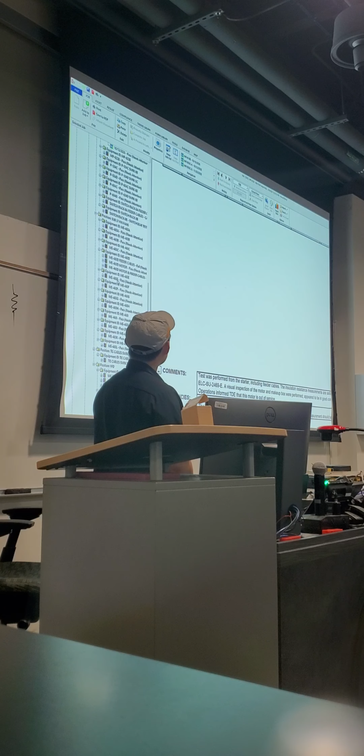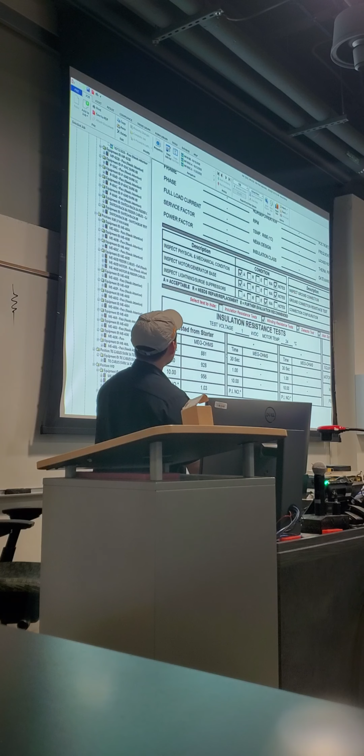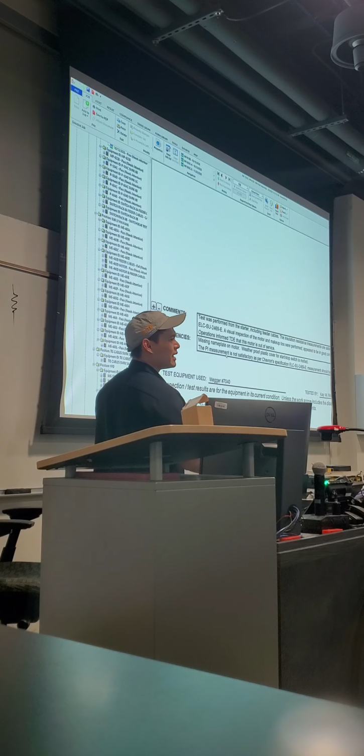I think for extra, you put a missing nameplate on the motor. Yeah, missing nameplate on the motor. And so, in this case, maybe we have historical data or maybe a sister motor and we'll know the system well enough from one line and stuff to be able to say, okay, this is your nominal, so we know to test it at this. But if it burned up in the fire or is illegible, well, standard 20% overage for that. We'll replace it.